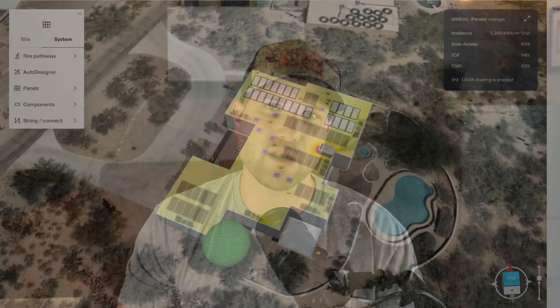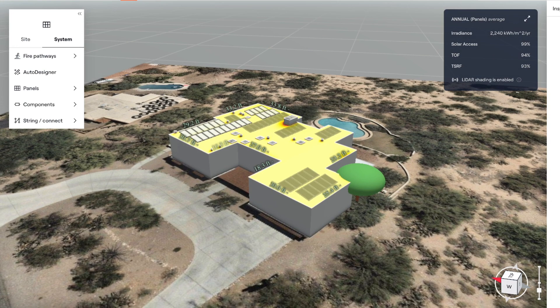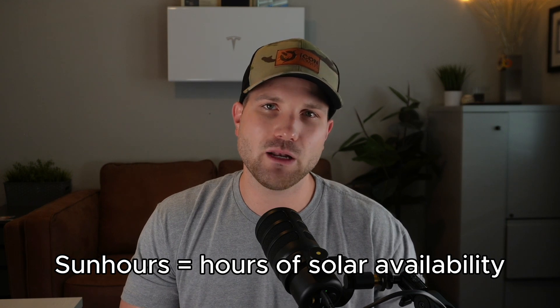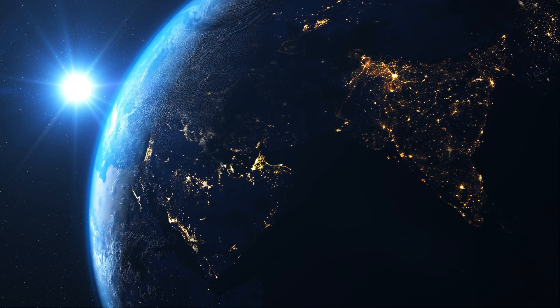In this scenario, we have 20 panels at 425 watts each, giving 8,500 watts total of available power. The amount of time these panels are exposed to sunlight, as well as the sun intensity, will dictate our total kilowatt hours generated — we commonly refer to this as sun hours or solar availability. Your roof direction, panel tilt, shading, and the part of the world you live in all play a role. Here in Tucson, Arizona, we have great sun hours, and we could probably expect an 8.5 kilowatt system to generate about 14,000 kilowatt hours per year on average. So on a solar proposal, you would know that your system is rated for 8.5 kilowatts and it can generate 14,000 kilowatt hours a year.